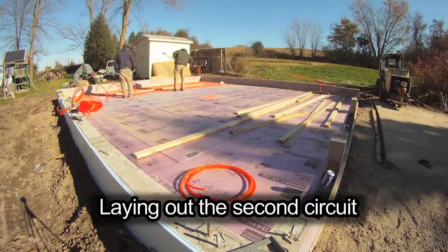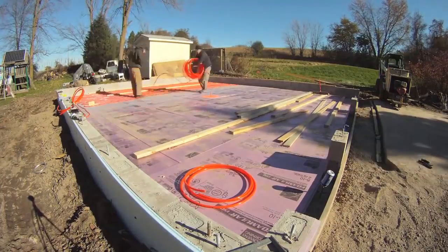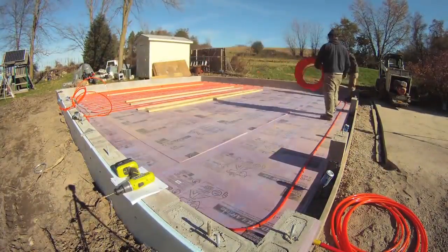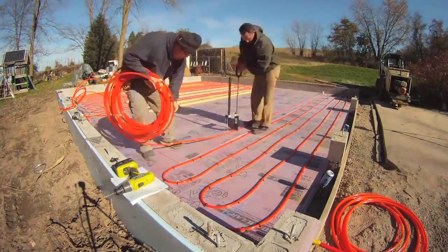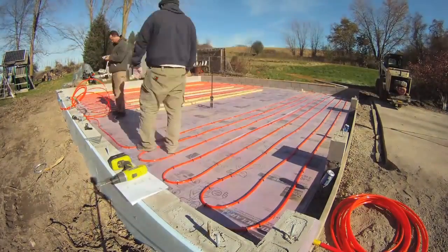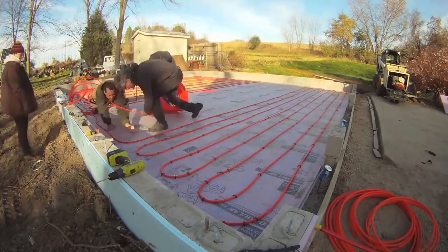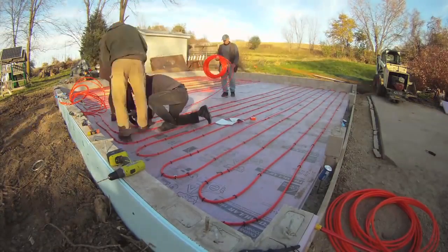After that we put in the PEX tubing — almost 800 feet of half-inch PEX, and frankly that was quite a bit of work. One thing I'd do differently is to make sure to get some sort of a tubing unroller device. It's a giant coil and you can't just pull it off; you actually have to unroll it as you go. Having a rotary device to help unroll it would be good if I did this again.